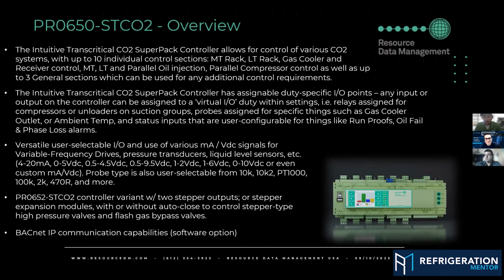It might happen that you turn on a suction group and it seems to be running fine, but it's actually going through that run proof process, and then it locks the compressor out and throws an alarm, and then it'll move to the next compressor and it'll lock that one out after a while as well. And what you'll find is that those two compressor run proofs were completely swapped around, and that was the issue the whole time. We actually run into a lot of that. I've spent way too many hours on the phone just trying to talk through that whole process with people. It's amazing what just a couple wires being swapped at the factory can do. So for sure. So it's just the wiring. That's it, right? The couple wires. Yeah. Just a couple wires.